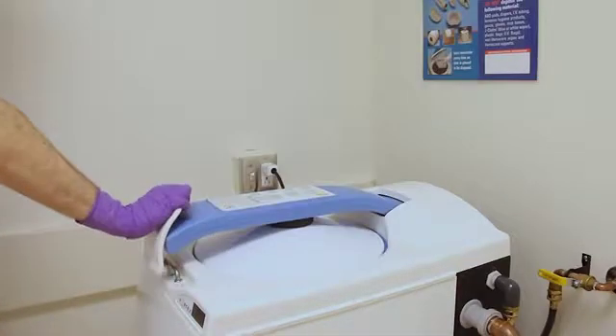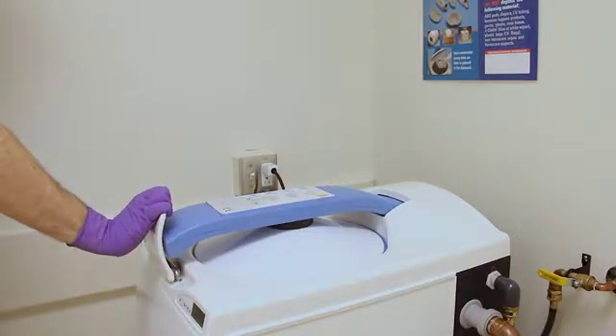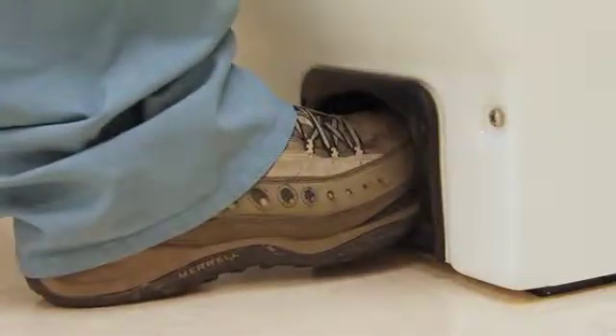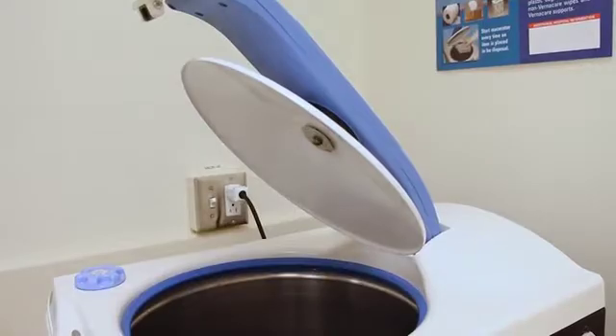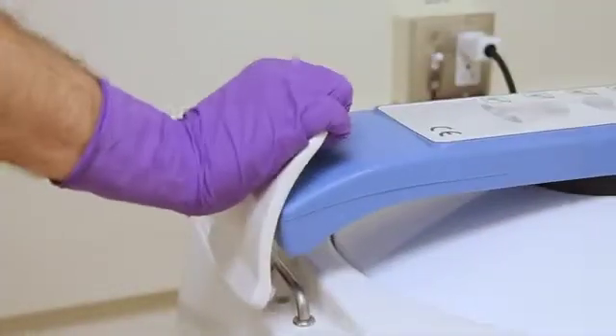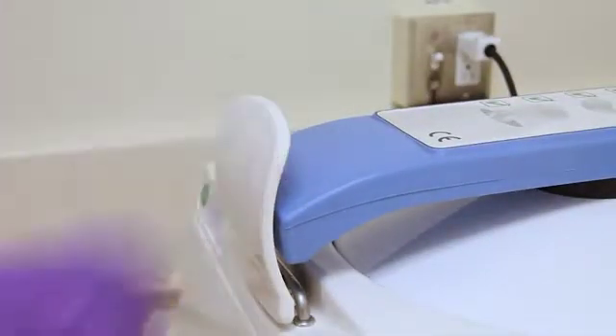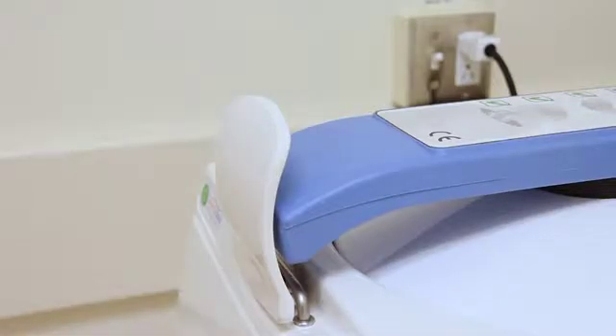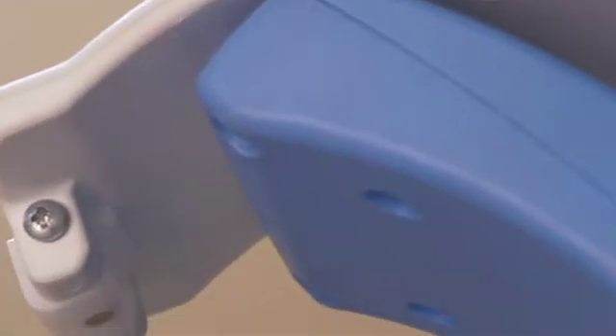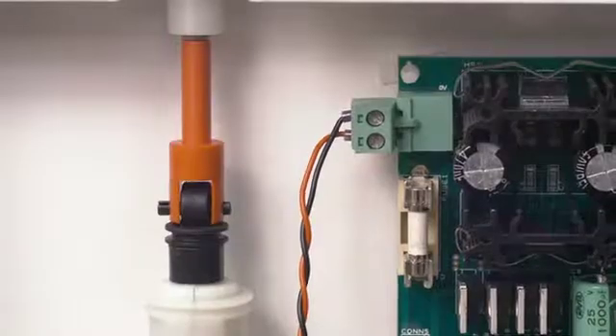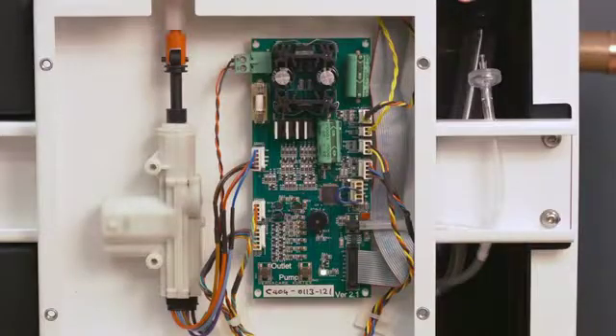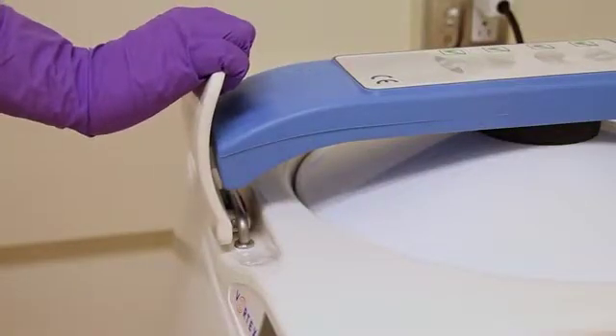Upon closing, the lid is locked and will remain locked until the infrared foot sensor is signaled. As a safety precaution, if the macerator has commenced a cycle, the lid will not open until the end of the cycle. When the lid is closed, a small magnet located in the lid handle signals the Hall effect sensor located beneath the top panel that the lid is closed. The actuator is then activated and a locking pin moves into the lid handle, locking the lid.